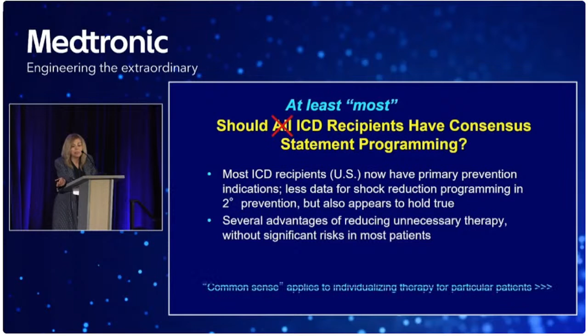Dr. Swerdlow and others did publish some cases reported where evidence-based programming may not always apply. So if you're using a study from one manufacturer and you throw it into a pot and you program, they're not all the same, right? Each of the algorithms is a little different. If you're using a device and a study that used Medtronic devices, that's easy because you're using the same manufacturer. But what we had initially done is publish an online supplement where all the manufacturers looked at this and said, how does this consensus statement apply to your device?